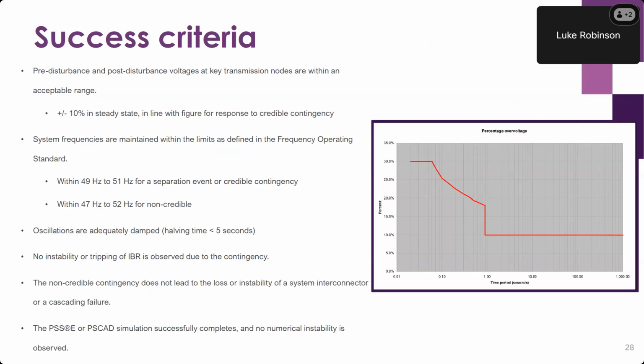I'll just talk briefly about some of the success criteria. For the risks that we're studying, we want to achieve the following success criteria. If we're looking at a credible contingency event, the voltage should not rise above the line shown in the figure here. That shows what the voltage response should be in the time after the fault. For a non-credible contingency, it's more lenient in the time responding to the fault, but it has to return to plus or minus 10% of the normal voltage. In terms of frequency, we're looking to maintain the frequency within 49 Hertz to 51 Hertz for a credible contingency and 47 Hertz to 52 Hertz for a non-credible contingency for the mainland system.